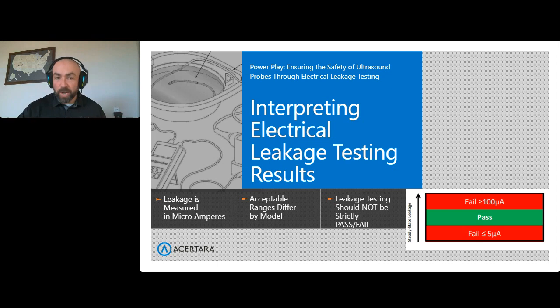Ensure that you understand what the acceptable ranges are, because those do differ by model. And when electric leakage testing is strictly pass or fail, that is not a great solution. You want to actually have the specific values, what that probe is measuring, because if you're passing at 99 microamps and it's trending, the last three measurements have been 90, 95, 99, you want to pull that device from service and get it repaired before it actually starts failing. Also, pass or fail devices tend to not have this display. You want to make sure that you actually know what the value is, so that it's tailored specifically to the device that you're measuring.